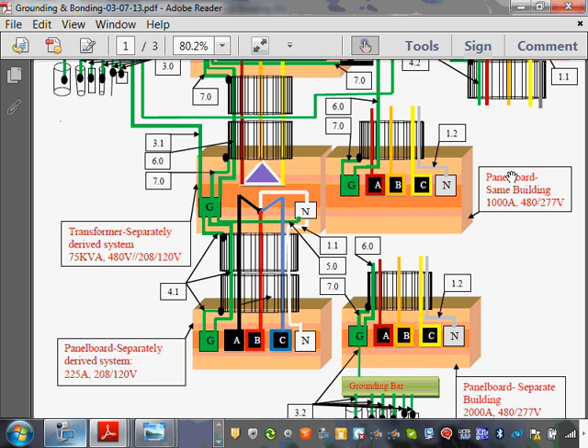But if I remember right, I thought this isolated grounding electrode system is allowed to go all the way to the service. It's allowed to. So I don't see it. You can take it all the way to the service, as long as you ground equipment. So you basically treat that as a drive. Yeah, but I see his point though. But yeah, you can pull it all the way. Okay, so we got that one. Good point. So we grounded the grounding electrode conductor, guys.